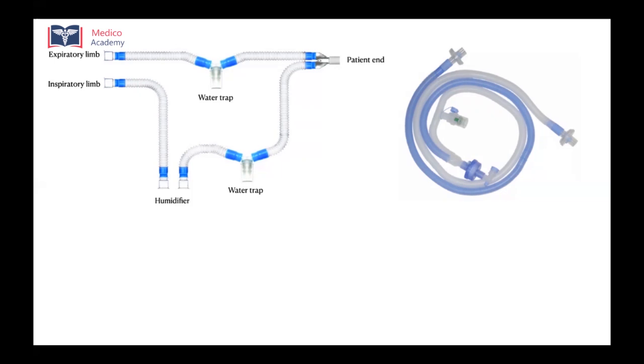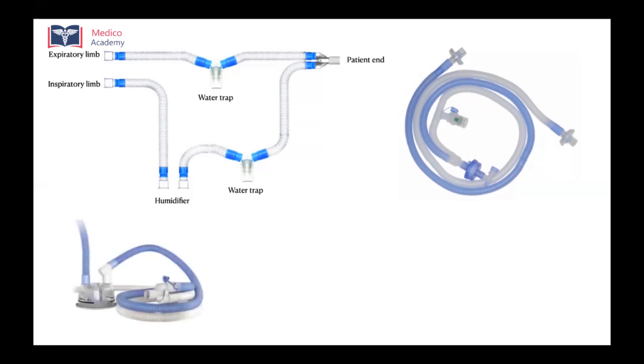HME is a heat and moisture exchanger, which is a passive humidifier. So this third picture, which has appeared now, shows an active humidifier. You can see a humidification jar in which you can fill distilled water. And this jar is heated. The water in the jar is heated so that the inspired gases remain warmed as well as humidified before they reach the patient.